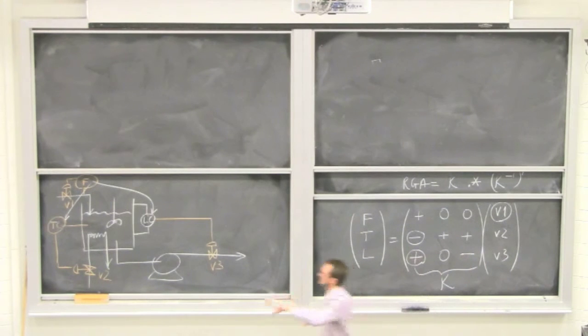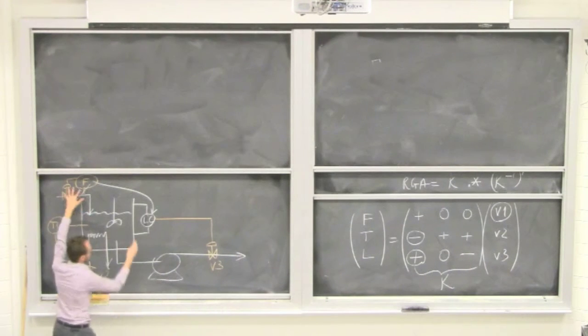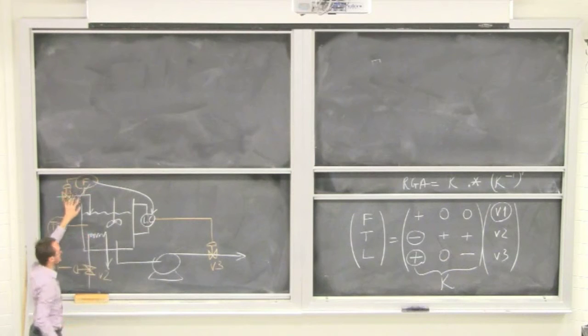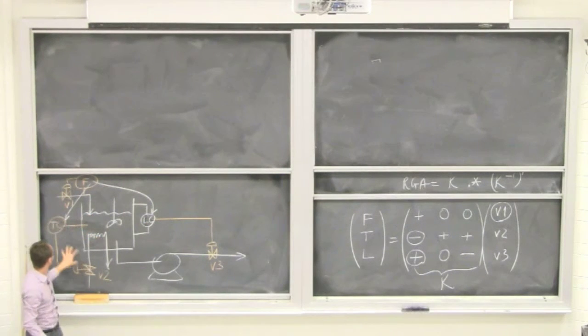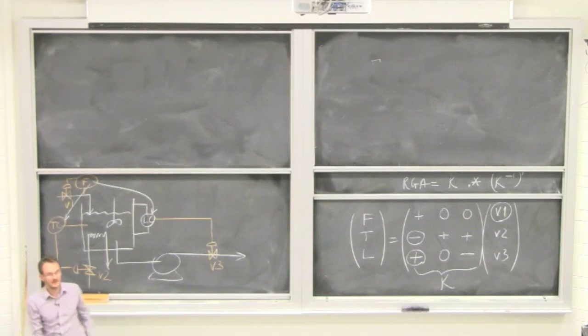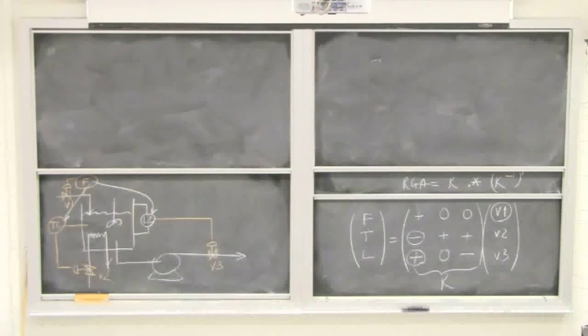It's further upstream, right? So you can't get your level coming back around at you and affecting flow. You can't get temperature coming back around you and affecting flow either. So it's a one-way interaction. That's a term that we see. And we like one-way interaction because that helps find our control loops for us. It eliminates this idea of interaction.